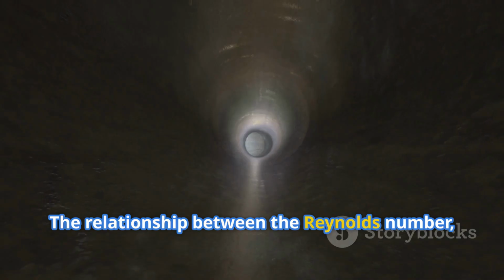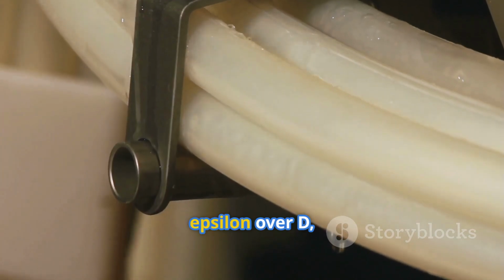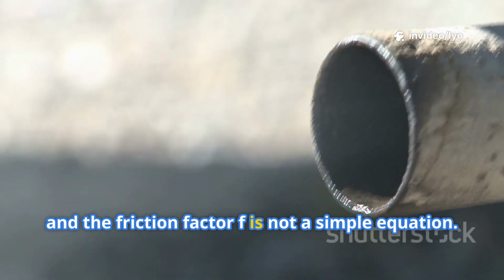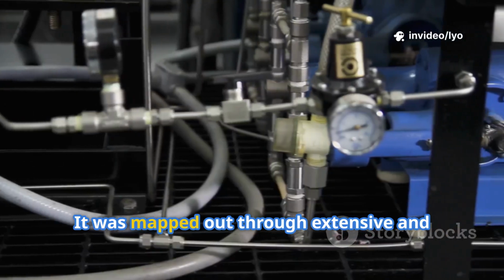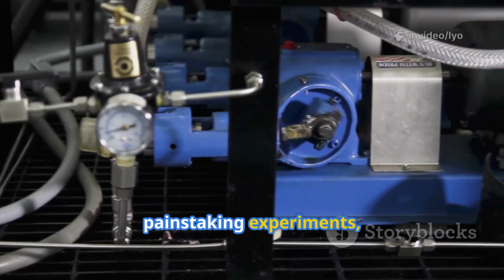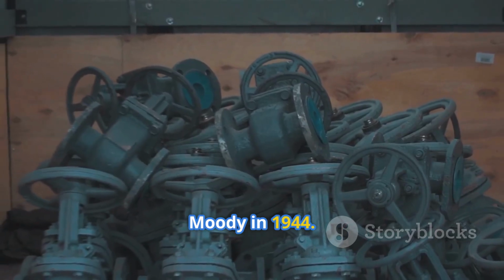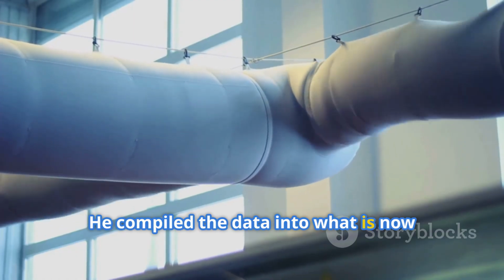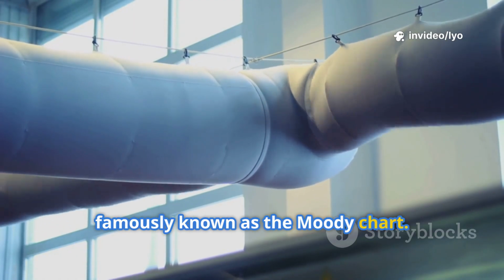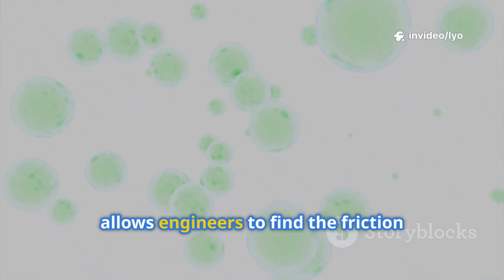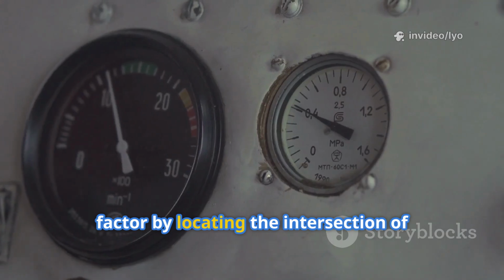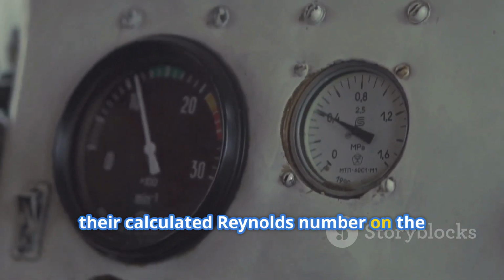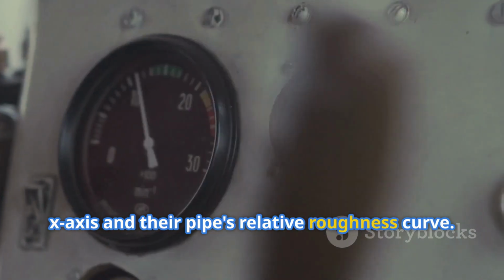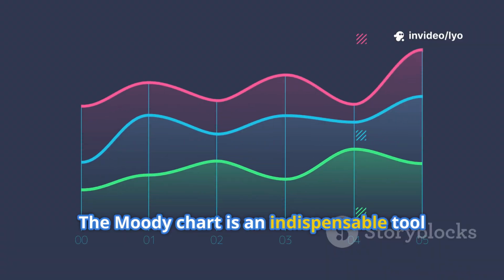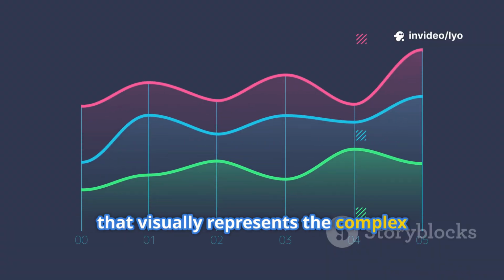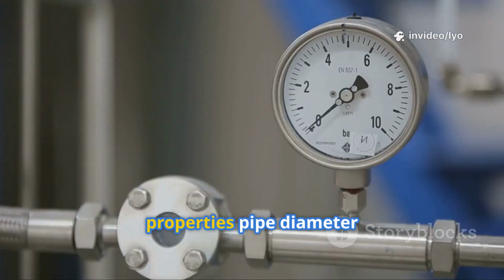The relationship between the Reynolds number, Re, the relative roughness, epsilon over D, and the friction factor F is not a simple equation. It was mapped out through extensive and painstaking experiments, most notably by Lewis F. Moody in 1944. He compiled the data into what is now famously known as the Moody chart. This chart is a graphical tool that allows engineers to find the friction factor by locating the intersection of their calculated Reynolds number on the x-axis and their pipe's relative roughness curve. The Moody chart is an indispensable tool that visually represents the complex interplay between flow velocity, fluid properties, and pipe diameter.